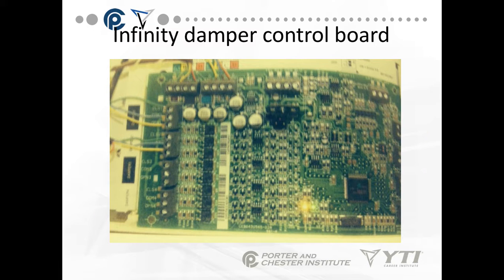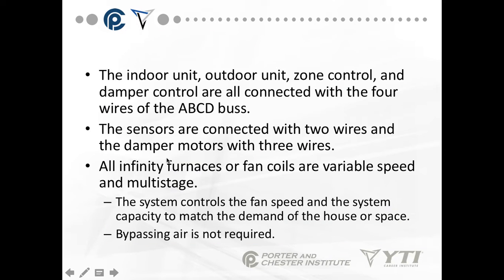This is an example of the Infinity control board — very solid-state components, with all wiring done on terminal blocks using a small thermostat screwdriver. The indoor unit, outdoor unit, zone control, and damper control are all connected with the four wires of the ABCD bus. The sensors are connected with two wires, and the damper motors with three wires.